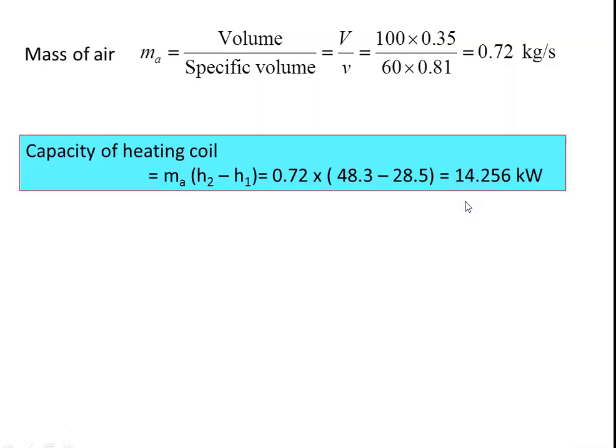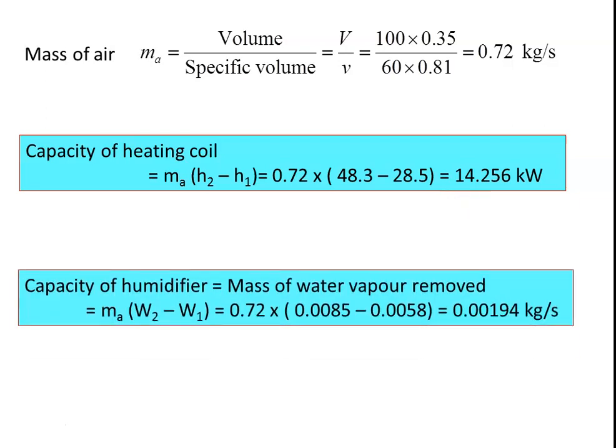Capacity of the heating coil = ma × (h2 − h1) = 0.72 × (48.3 − 28.5) = 14.256 kilowatts. Capacity of the humidifier (mass of water vapor added) = ma × (w2 − w1) = 0.72 × (0.0085 − 0.0058) = 0.00194 kilograms per second.